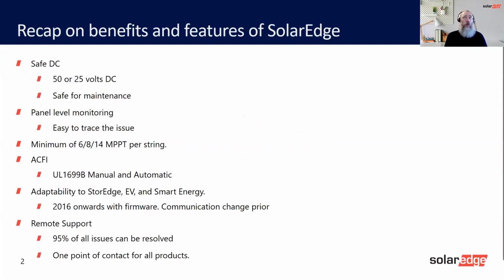So one of the important things with SolarEdge, you've already picked up on the poll, is the module level electronics, but there are other features that are equally as important. And just to recap on the benefits of these, Safe DC, as we see, we have lots of benefits with SolarEdge, and these are one of the advantages with Safe DC. You're probably familiar with arc fault circuit interruption or arc fault detection. It seems to be quite a common phrase these days that you see from manufacturers. And detecting an arc is great because that allows you to know there's an arc. But unless you can do something about that arc, it doesn't really help.